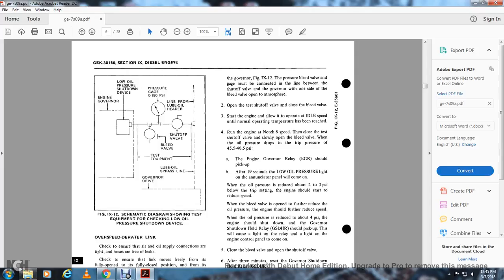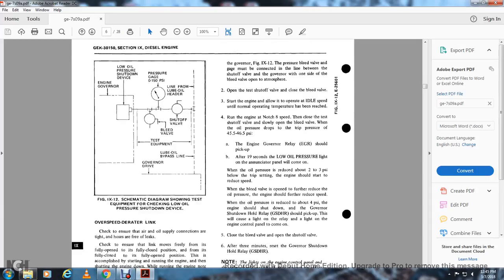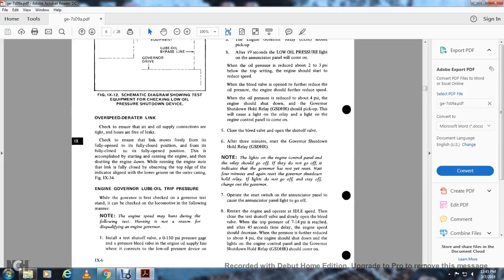When the oil pressure drops to the trip pressure of 45.5 to 46.5 PSI, the engine governor relay (EGR) should pick up. After 19 seconds, the oil pressure light on the annunciator panel will come on when the oil pressure has been reduced to 2 to 3 PSI below the trip setting. The engine should start reducing speed. When the bleed valve is opened further to reduce the pressure, the engine should further reduce speed. When the oil pressure is reduced to about 4 PSI, the engine should shut down. The governor shutdown hold relay should pick up, causing a light on the engine control panel to come on. Close the bleed valve and open the shutoff valve. After three minutes, reset the governor shutdown hold relay.